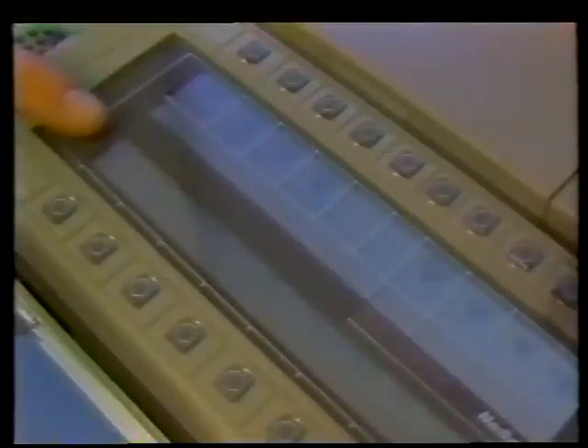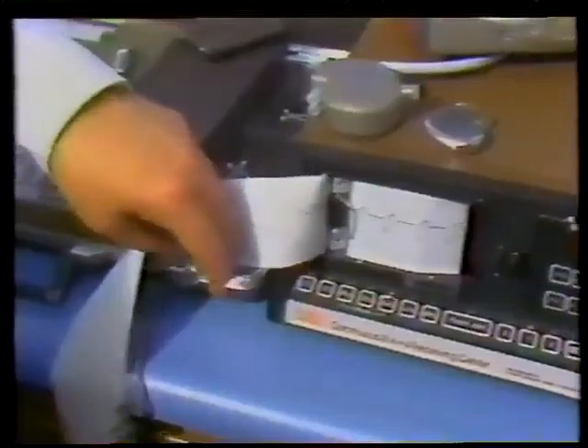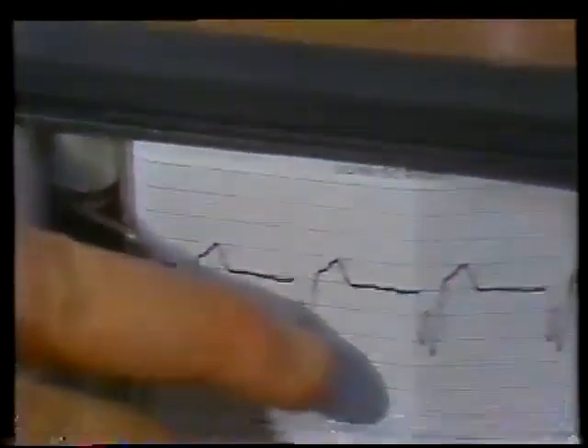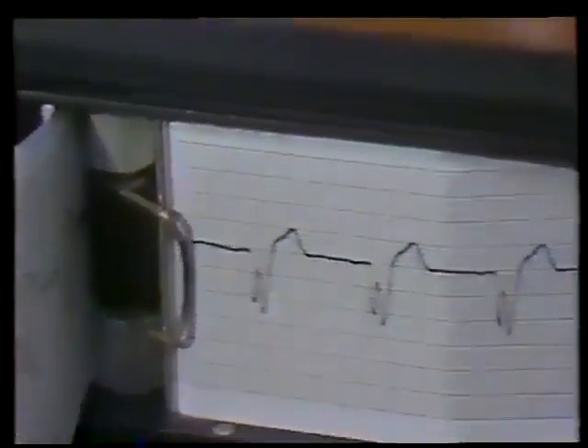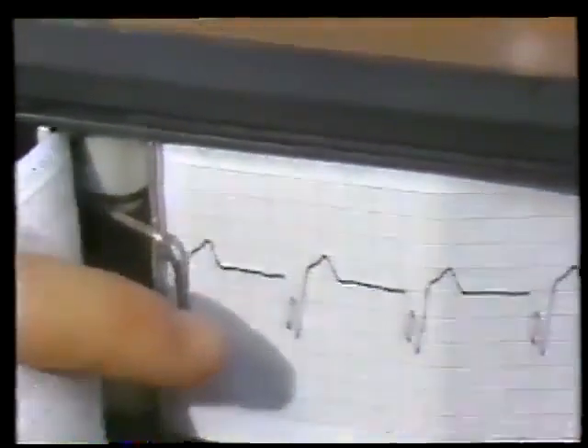As you can see, not only can we program the pacemaker, but the pacemaker came back and said through the programming head that indeed the pacemaker has been programmed adequately, and that the pacemaker is functioning exactly as we said it. And indeed, you can see that the heart rate has picked up only because the electrical activity of the pacemaker is being seen here. It also shows that the upper part of the heart is working fine, and the lower part of the heart is requiring a little assistance from the pacemaker.